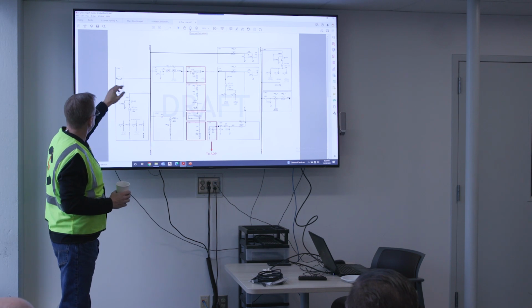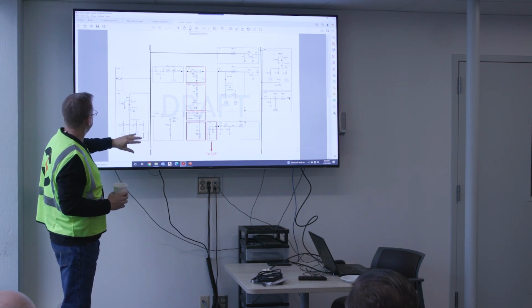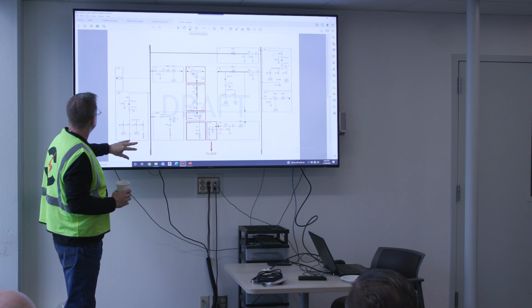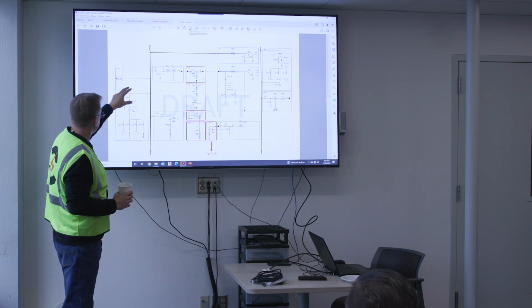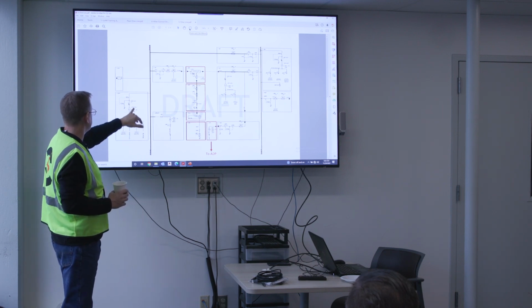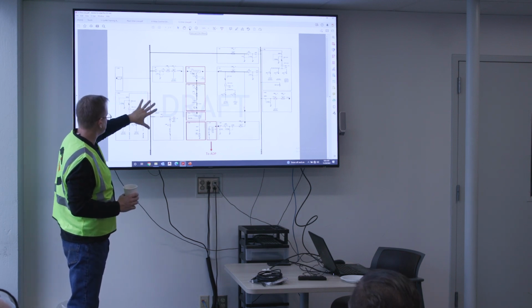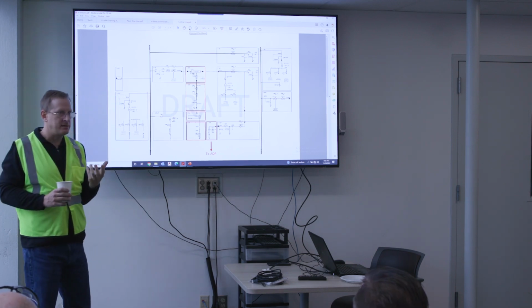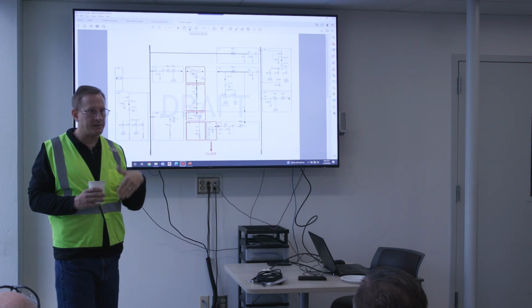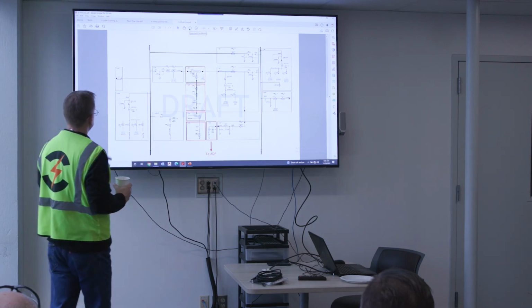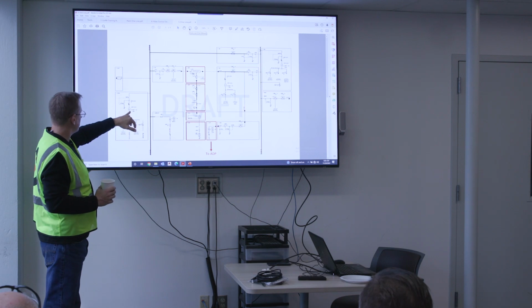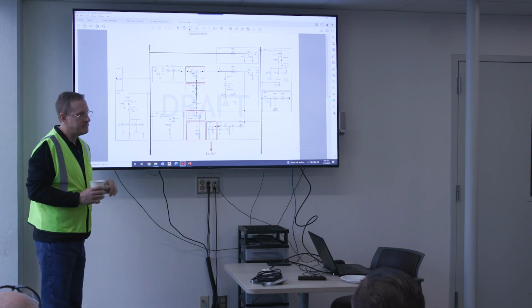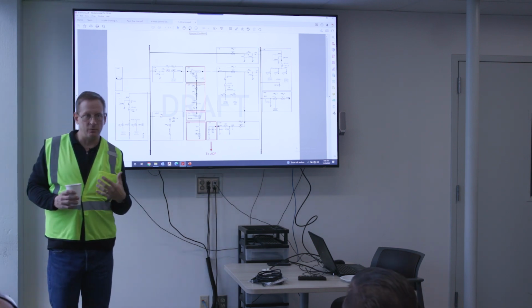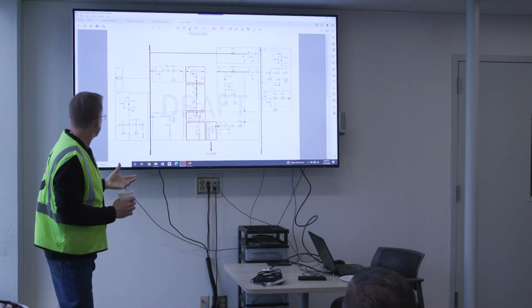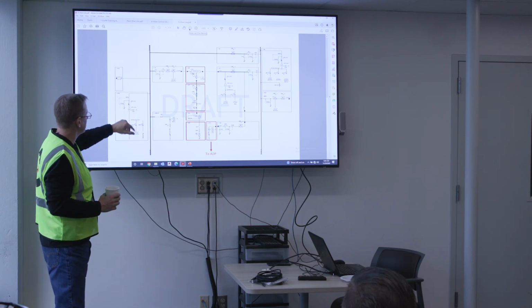If you look at the one line here, again looking at the utility coming in, this is where our sensing takes place for the utility voltage and frequency. This is all 4160 bus here, so in order to take the signal into our system, we have to knock that down to 120. You'll have some PTs from 4160 to 120 that knock down that signal so that we can monitor the mains frequency and voltage at a 120 volt level that goes into our DICON, as I mentioned. That's what this is doing here.